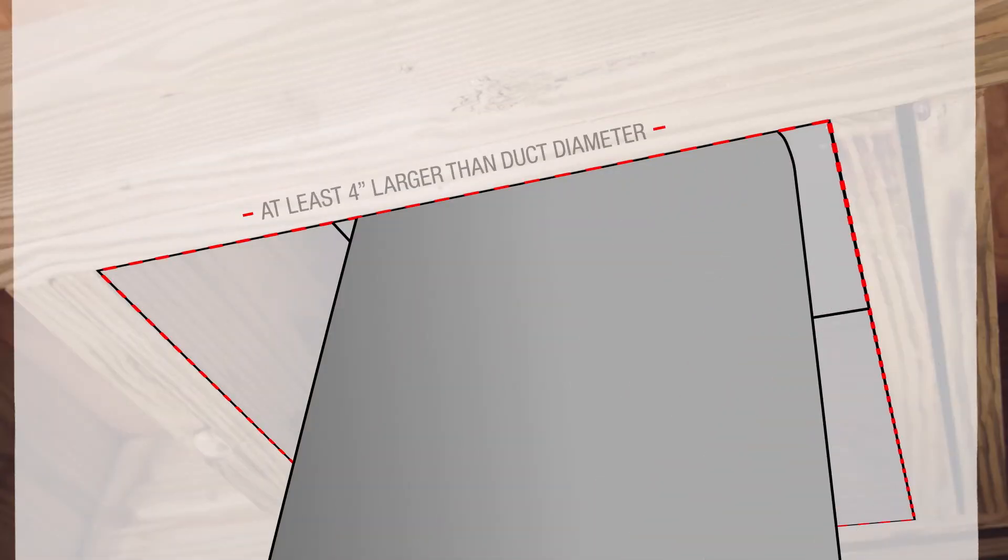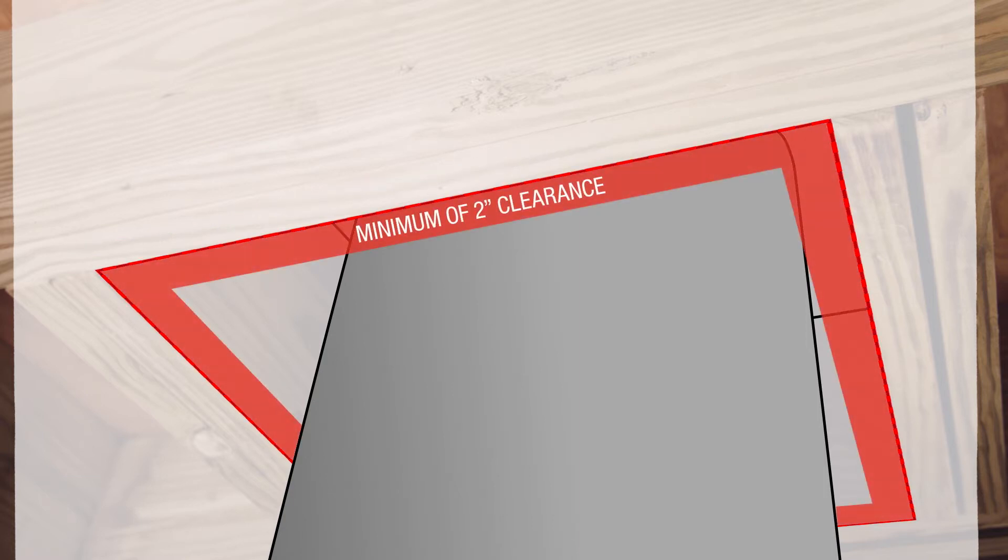The overall opening must be at least four inches larger than the outer diameter of the duct. The duct must be at least two inches away from combustibles at all times.